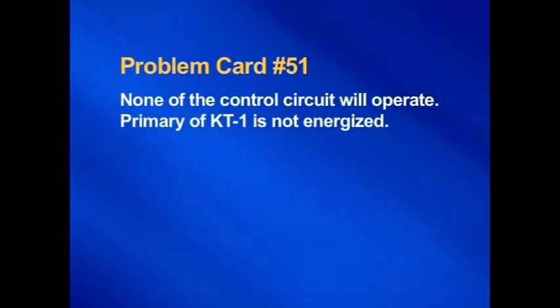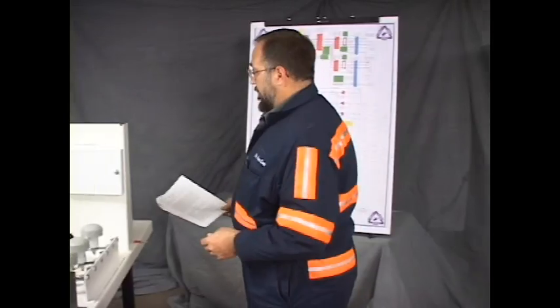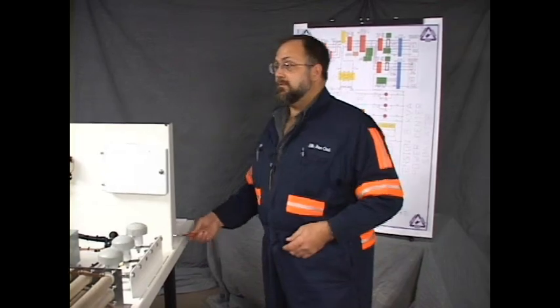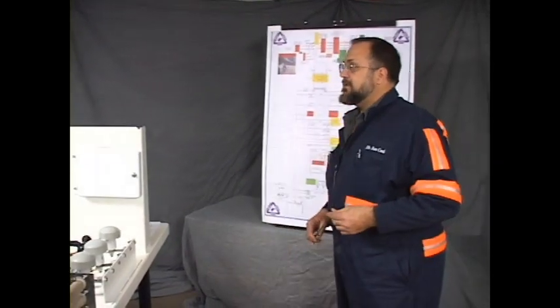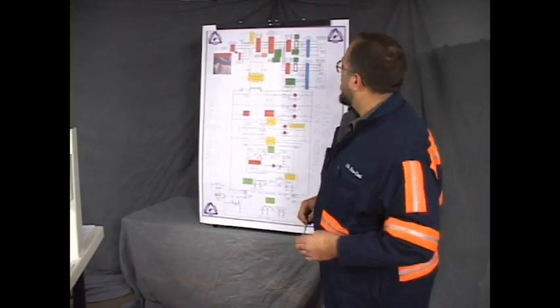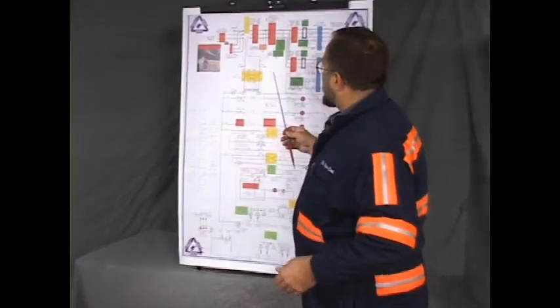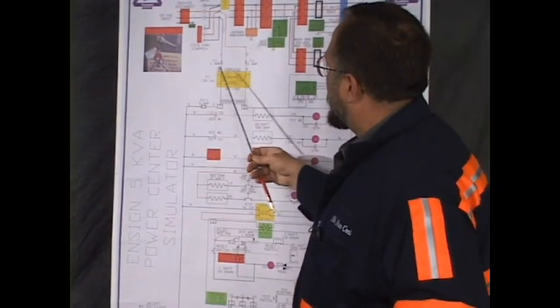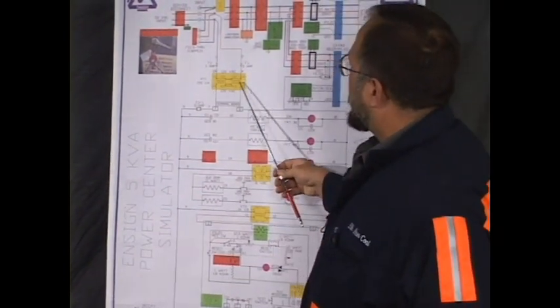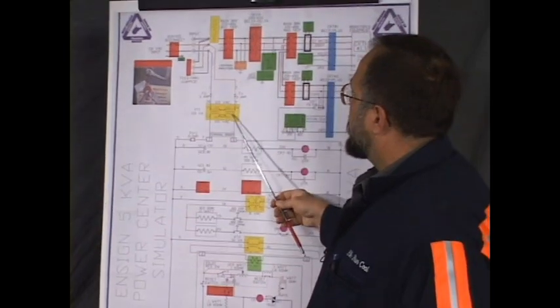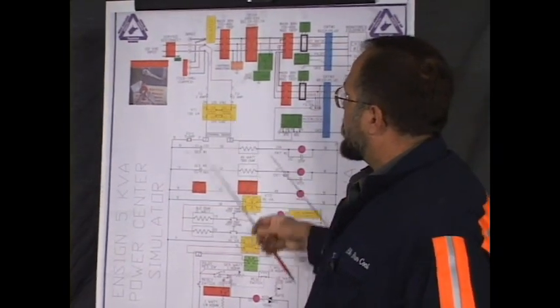The first problem, problem card 51, reads, none of the control circuit will operate. The primary of KT1 is not energized. That's a pretty big clue. The primary of KT1 is not energized. As before, when I showed you before, we said this is KT1 on the print. The primary is from the source, is not energized.